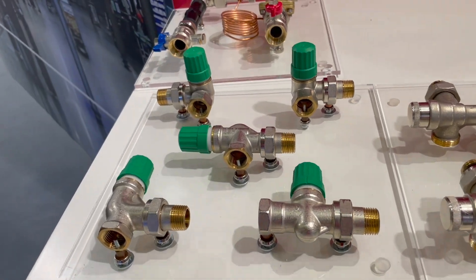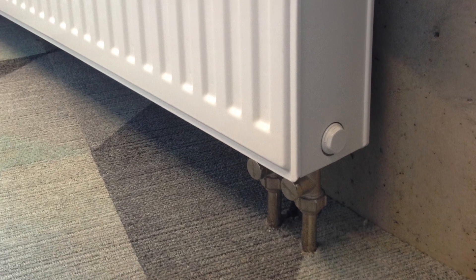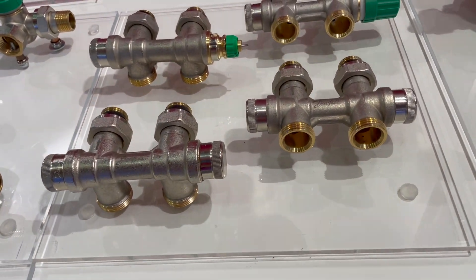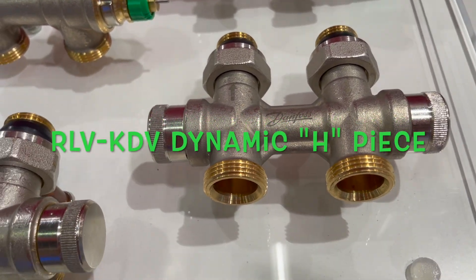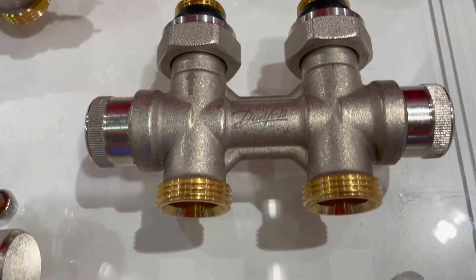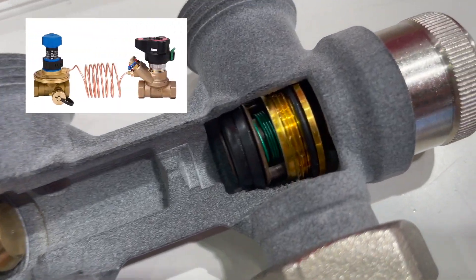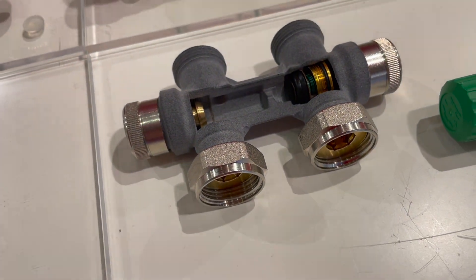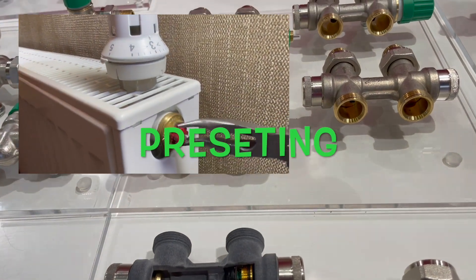Sometimes on projects we have radiators with side connection and radiators with bottom connection. For bottom-connection radiators, it is good to use dynamic H-pieces, called RLV-KDV. It looks like this and has a small delta-P controller inside, which keeps 10 kPa for each radiator.